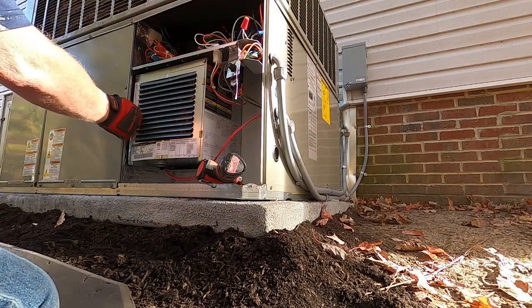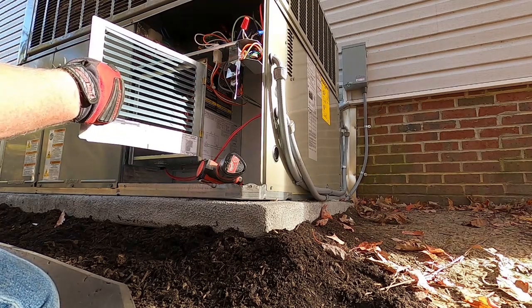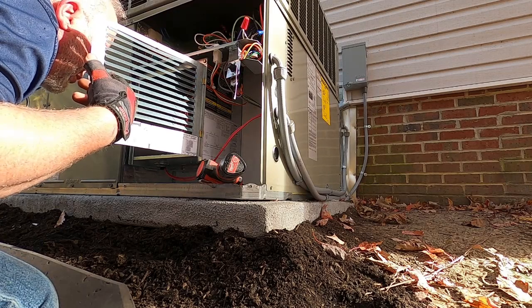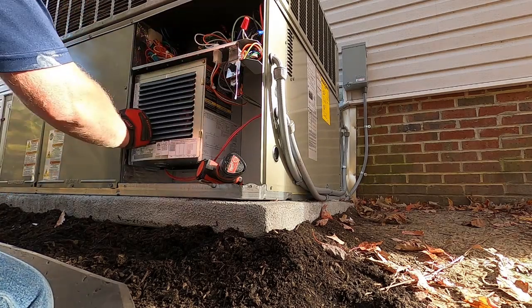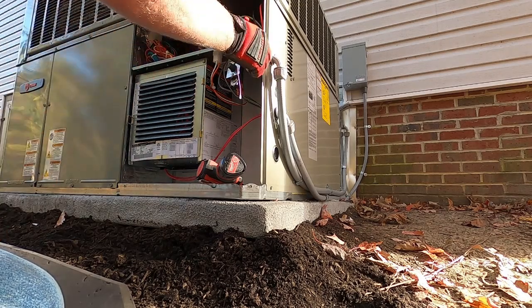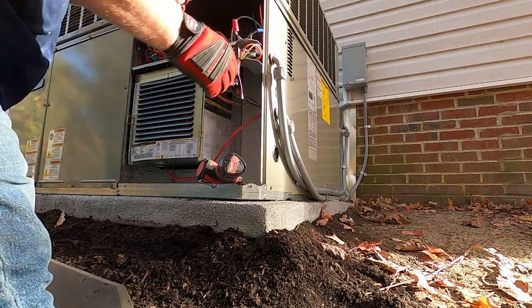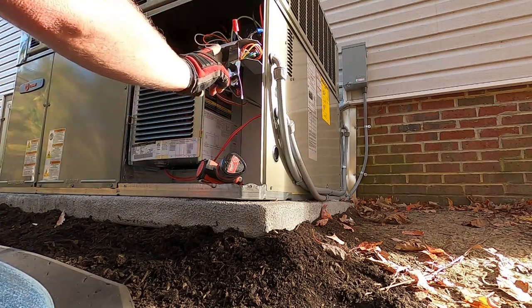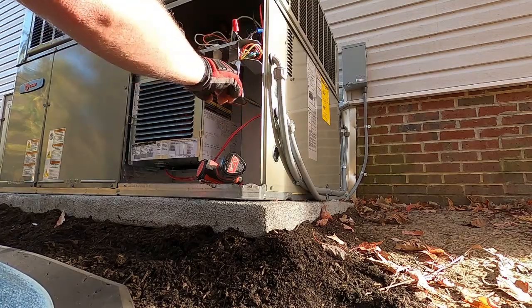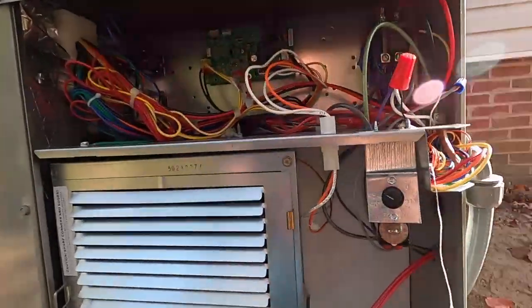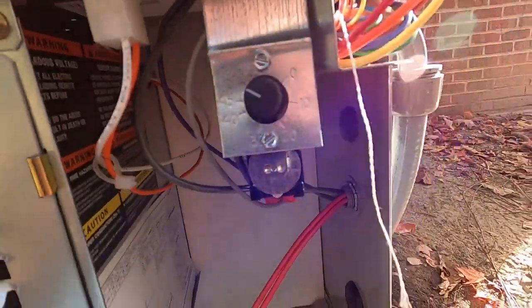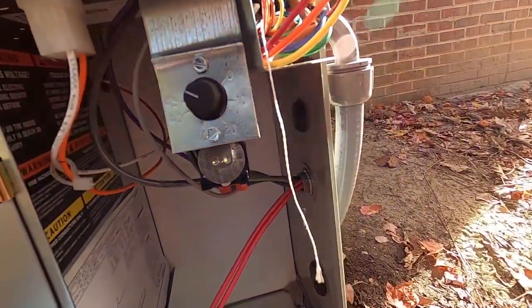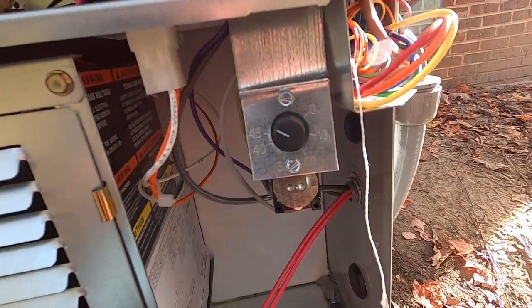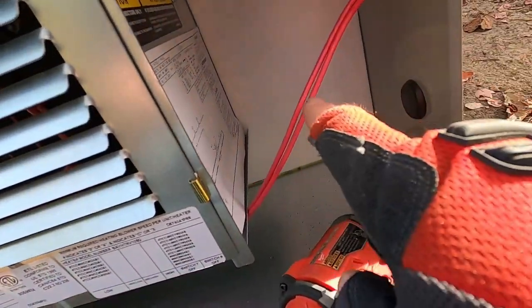Basically just a single stage heating and cooling package in it. We got 5 kW heaters in here. We're going to run all this and double check it to make sure all my wiring is correct. Got an outdoor temperature switch right here for our lockout control on the heat strips, but that one doesn't work. You got to have one that's got the external sensor you can run outside, because when this thing's closed up and the heat's running, the back wall of this thing gets warm, the inside of here gets warm, and there's a hornet flying around.